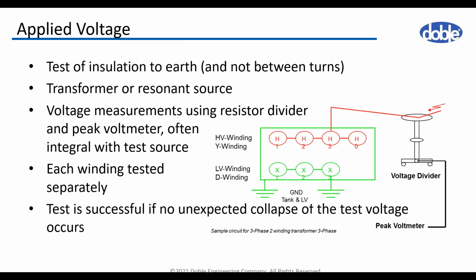The next test we will review is the applied voltage test. The purpose of the test is to check the main insulation of the transformer, and the voltage source for this test is usually dedicated regulating and step-up transformers. Manufacturers sometimes use a resonance test system for this test as well. The voltage is measured by voltage divider and a peak voltmeter. Each winding is tested separately.